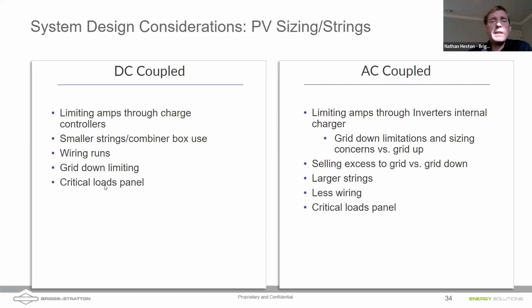An example where you wouldn't need a critical loads panel is if you're using a larger inverter like a SolArk 15K. You just have to keep in mind that the SolArk 15K is only capable of powering 15 kilowatts of load by combining battery and solar, and only 12 kilowatts when you're going straight from battery. So there are some limitations on the equipment. Of course, you can parallel multiple inverters. You can parallel our inverter to double that 6 kilowatts to 12, and you can parallel the SolArks to get more power out.